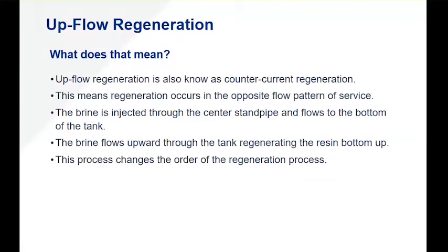Quite often, you will see this process used on twin tank systems because you absolutely have control over the entire process using soft water for regeneration. In upflow, you can start cutting into that reserve capacity and get more capacity out of the same tank. But if you do this too quickly, you fluff up the bed and lose the efficiencies. So upflow brining has to be done really, really slowly, or with a kind of a weighted disc that stays in place on top of the bed to keep it weighted down so it doesn't fluidize the top portion of the bed.